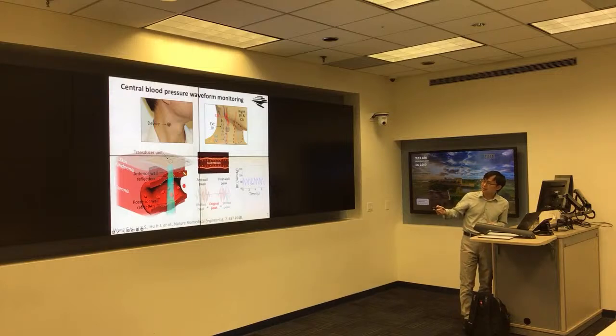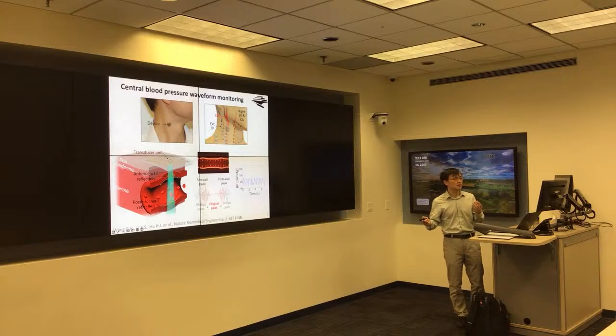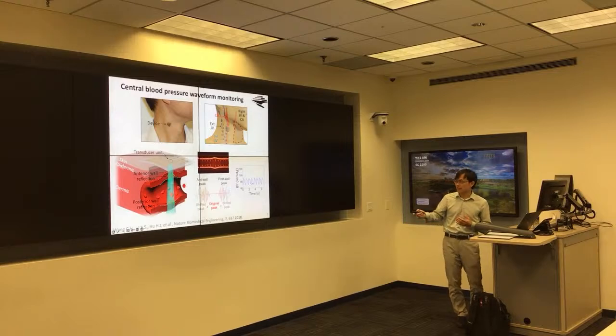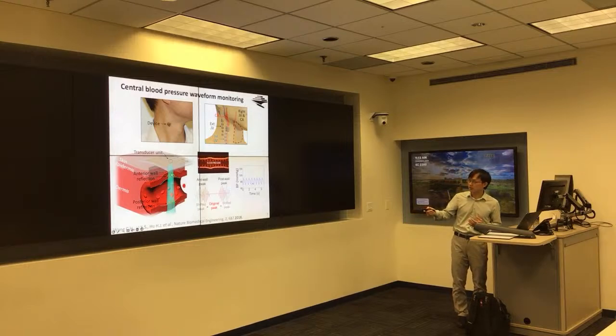And this is the mechanism showing how we can measure blood pressure using ultrasound. So imagine there is a transducer laid over this vessel, and it emits an ultrasound beam. This ultrasound beam will be reflected by those two vessel walls because of this acoustic impedance mismatch, right? Solid, liquid, liquid, solid. So there's a mismatch, so the ultrasound will be reflected most strongly at those two interfaces.